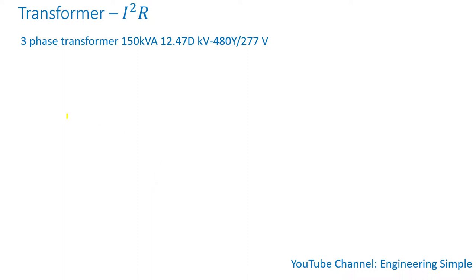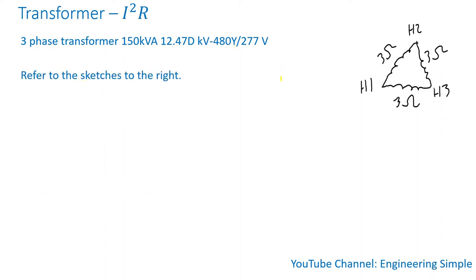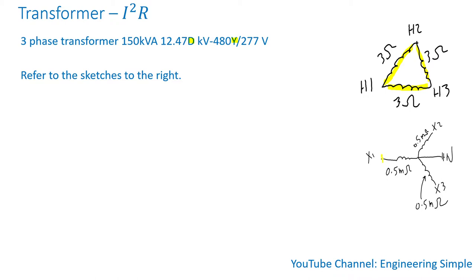Let's assume we have a three-phase transformer rated 150 kVA. The primary side is 12.47 kV connected as a delta, and the secondary side is 480 volts connected as a Y. Referring to the sketches on the right: the primary delta winding has a phase resistance of 3 ohms, and the secondary Y winding has a phase resistance of 0.5 milliohms.